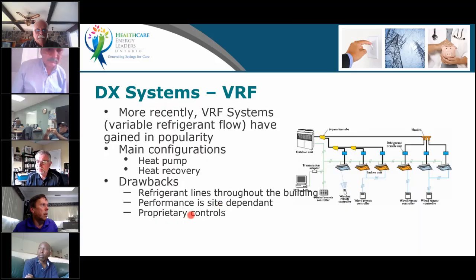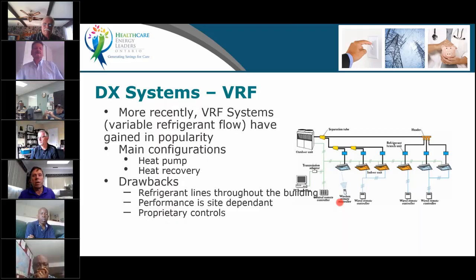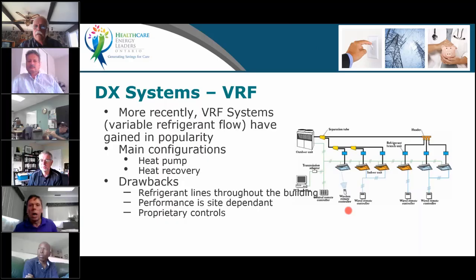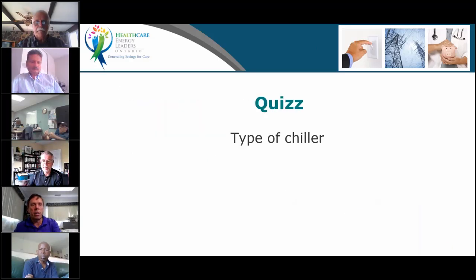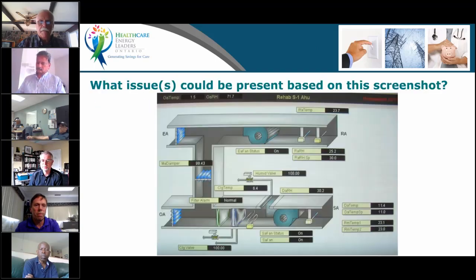If you have some of those, again, it is efficient, but the drawback is a lot of refrigerant. Performance is site dependent. And until recently, controls were a pain because it was really hard to centralize. Like I said, if you have that, it will likely be in the administrative area of the building because technically, CSA 317 would not allow that in type 1 and type 2 spaces. So I think it's 3:15, and the schedule says I'll pass that on to Jeff.